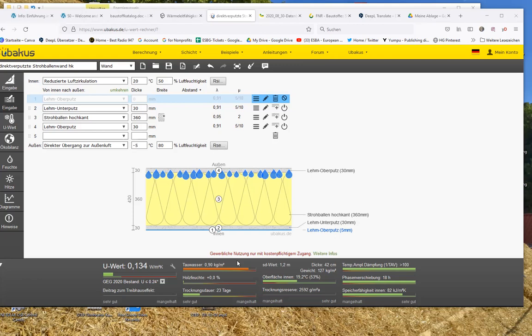The general principle for design of building constructions is that we need to have much bigger diffusion resistance on the inside and lower diffusion resistance outside, so that water doesn't condense here. And here, with the same layer inside and outside, we have the same resistance outside and inside. This is why, from the point of view of this diffusion review, it doesn't work very well here.